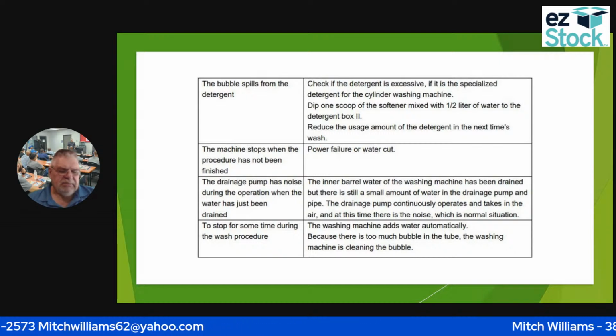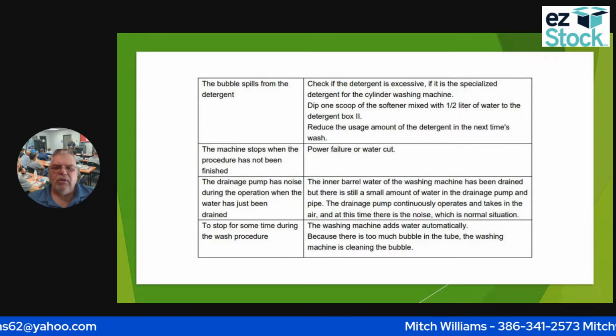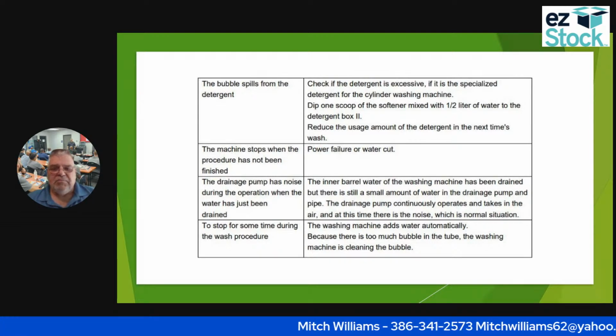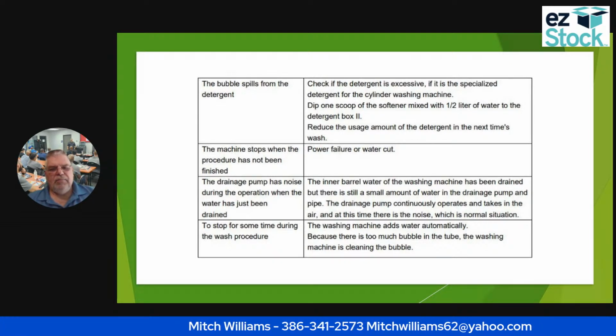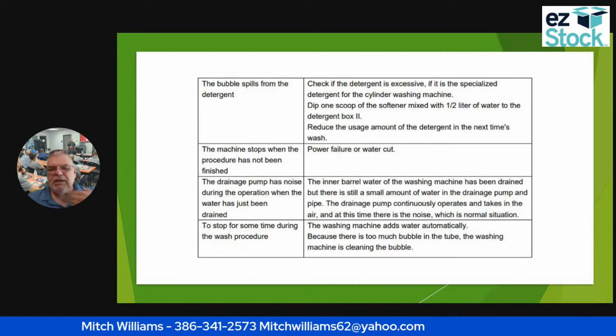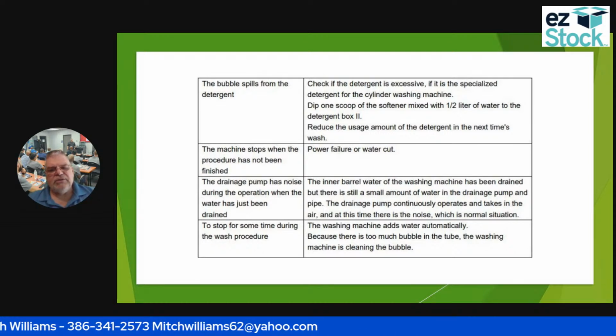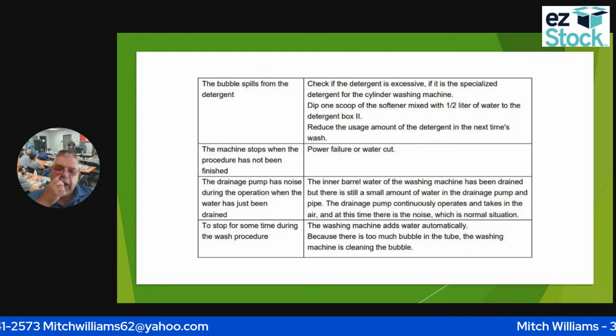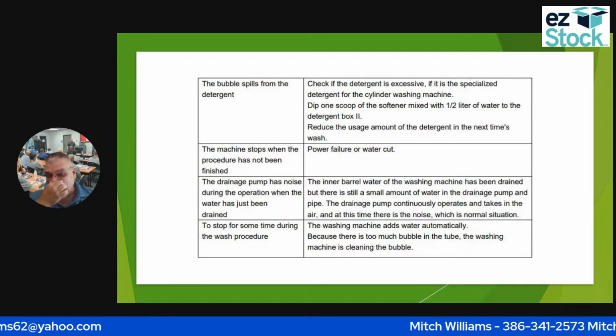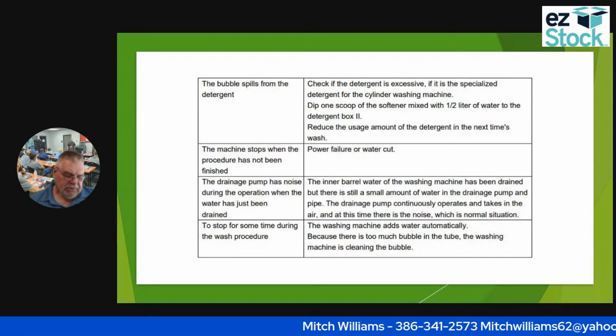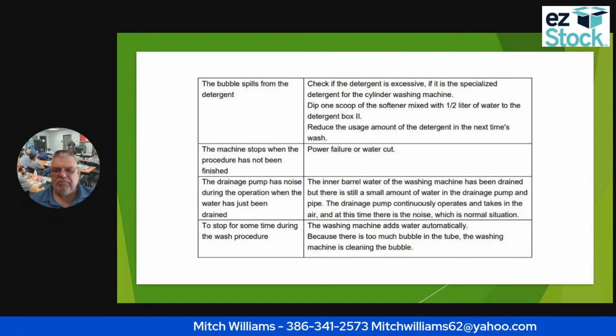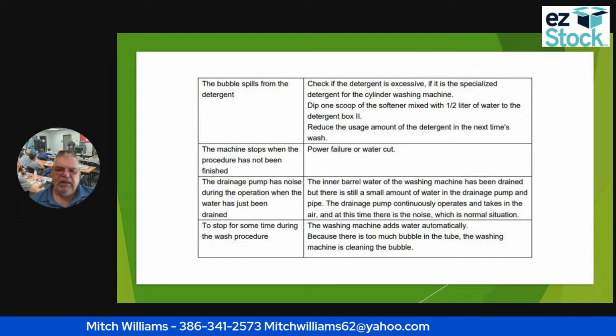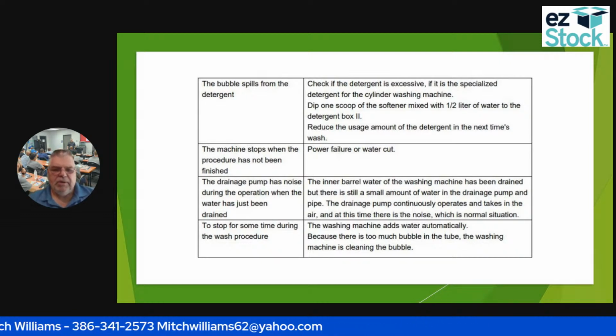So I'm going to check to make sure that I had no power failure or the water hadn't been cut off somehow. The drainage pump has a noise during the operation. So what I'm going to have to do is remove that drain pump, see if I've got something stuck in the drain pump. And if I don't have that, I'm probably going to have to replace that drain pump.